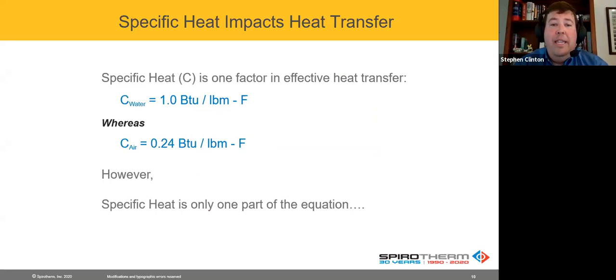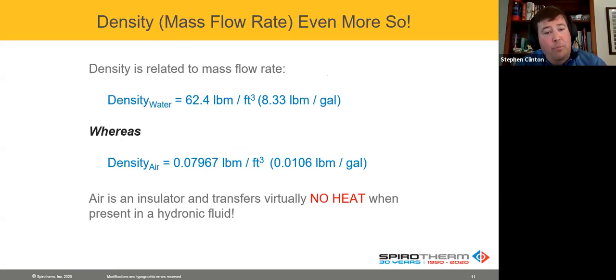A few years ago, when I started looking at this, I initially looked at the specific heat and thought, hey, water is 4 times that of air. So that's really what I'm going to key in on. But then as I thought about it even more, I thought, wow, the big difference is the mass flow rate, because water is much more dense than air. I think 840 times more dense. So basically, if I have 1 gallon of water, that's 8.33 pounds. 1 gallon of air is 0.0106. So basically, that is not transferring very much heat at all. So basically, again, it's an insulator.